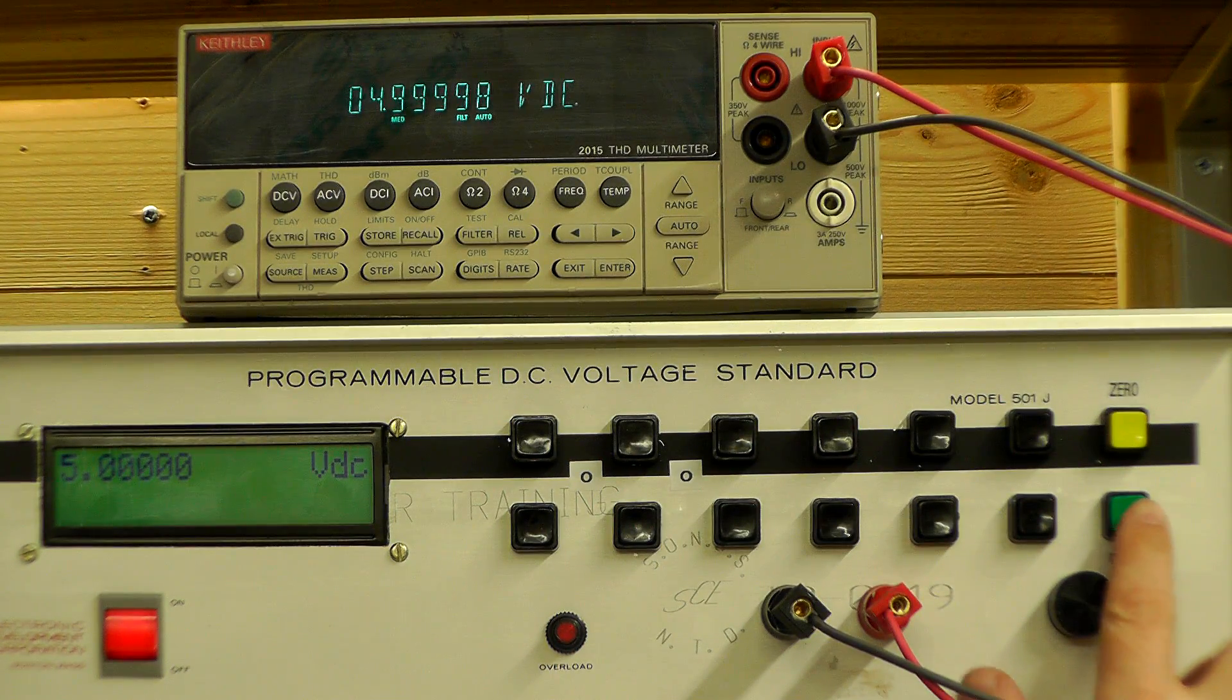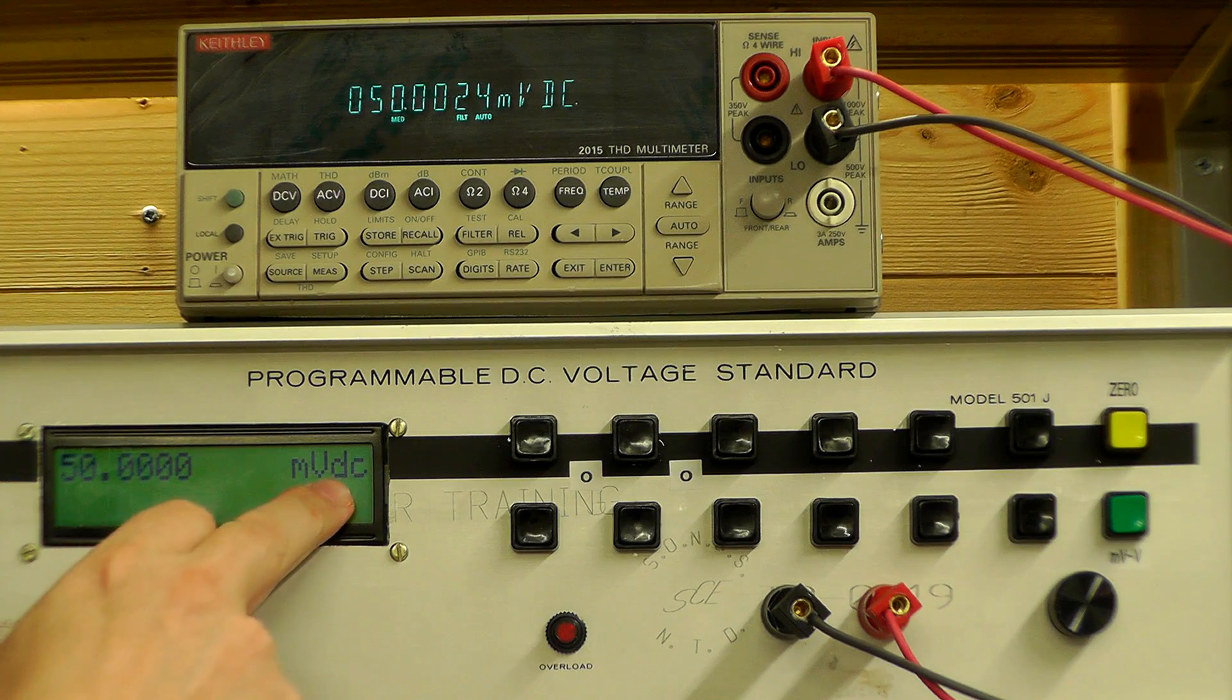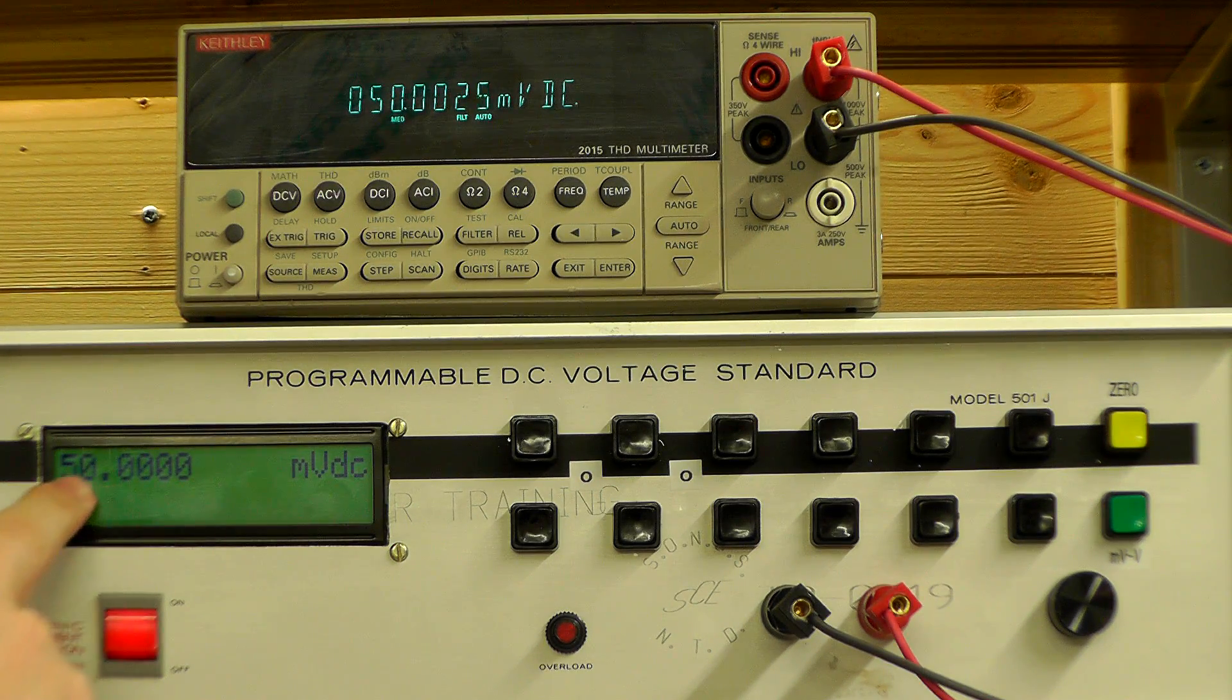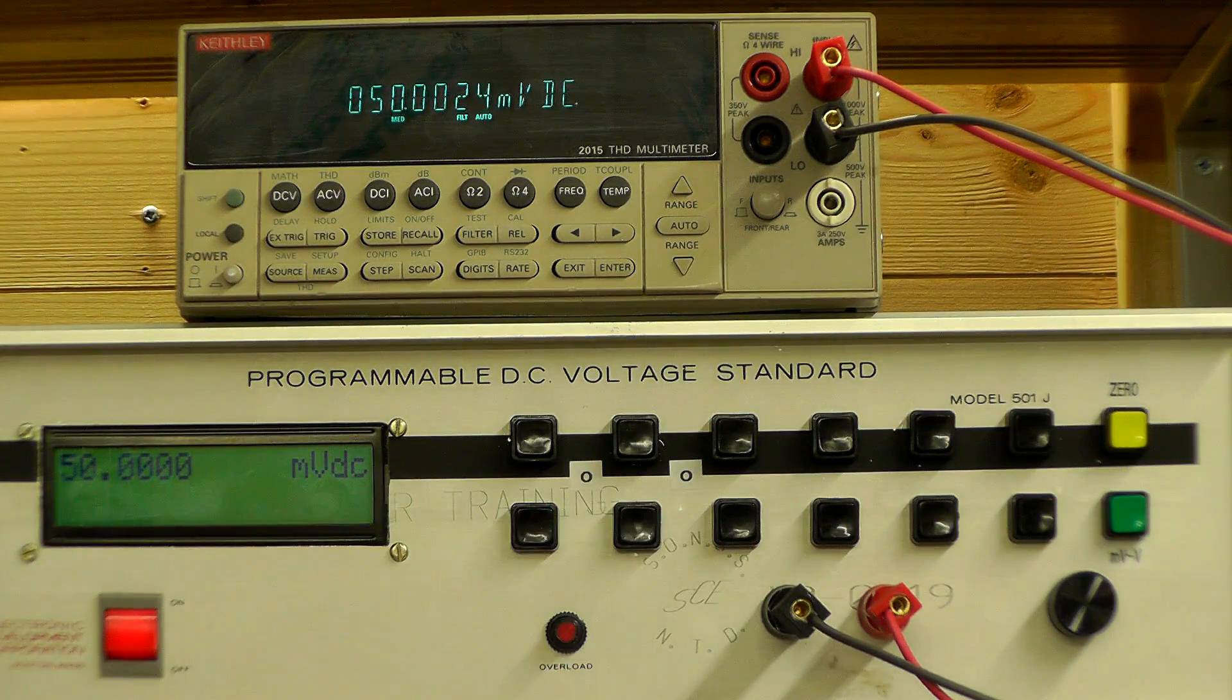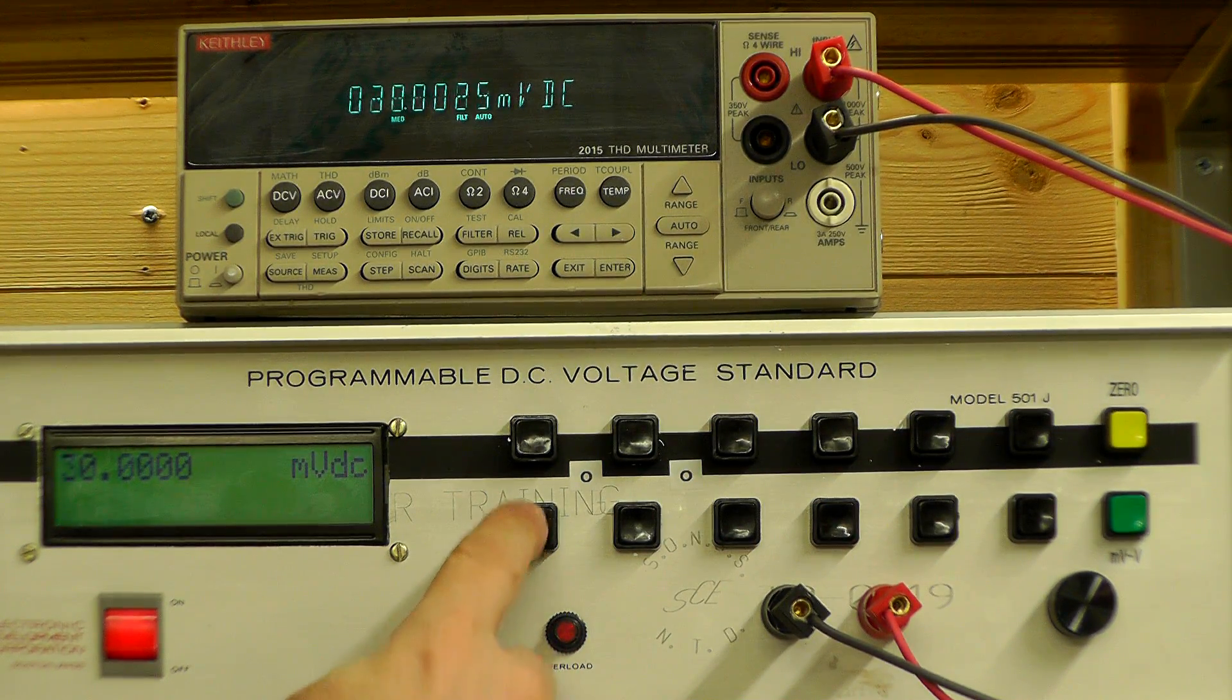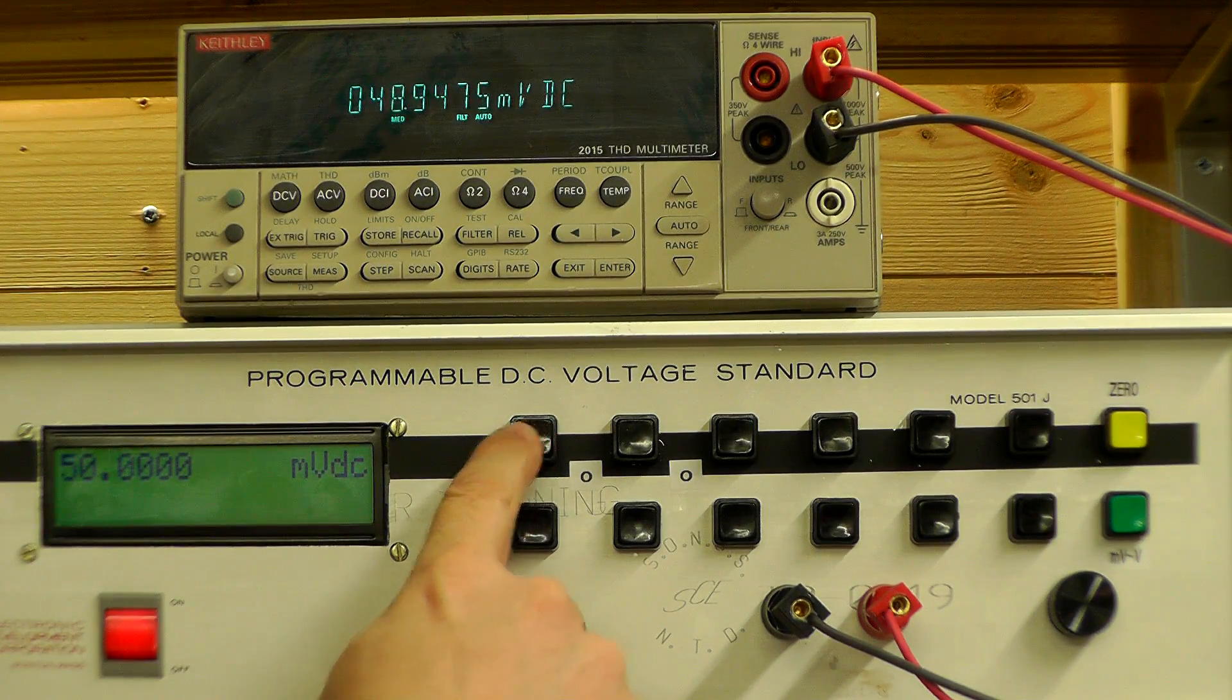And if I hit the push button here, we're in millivolt mode and you can see the decimal point shifted there. And that's again reading from the up down switches. Obviously I can go and press the push button here and you'll see the display changing there for the most significant digit.